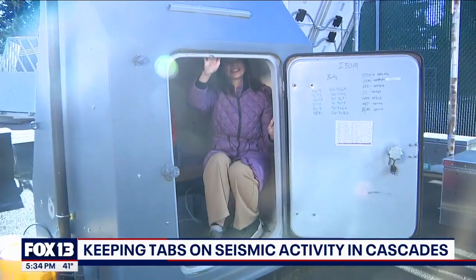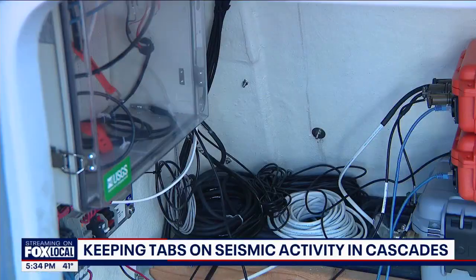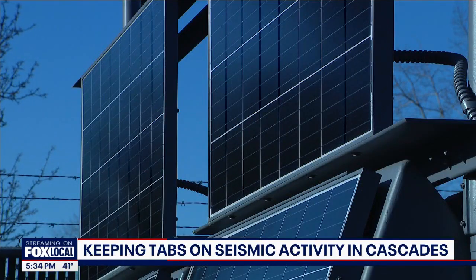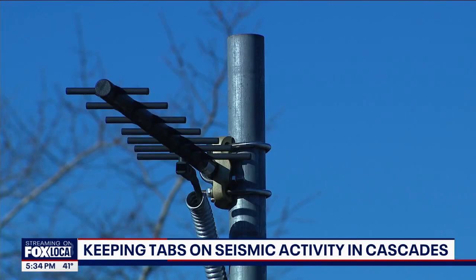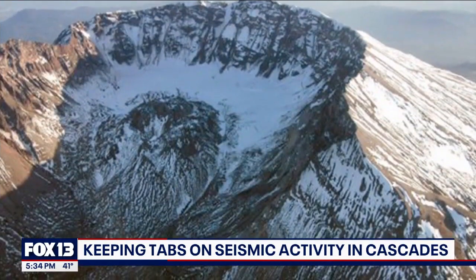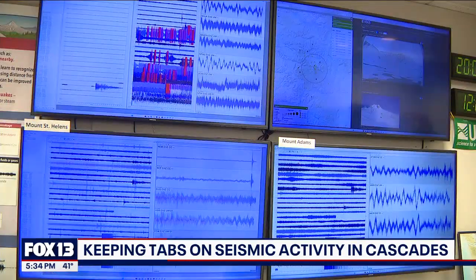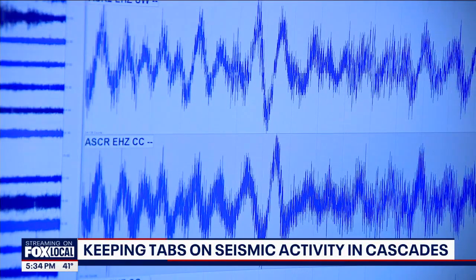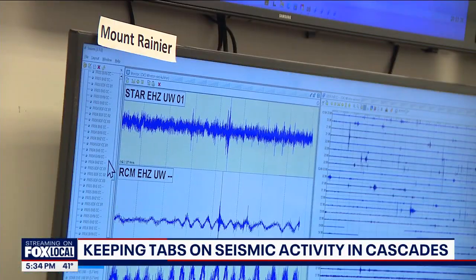We're not just learning how scientists track our region's active volcanoes — we are taking a quite literal inside look at a monitoring station. All that technology I just showed you, well, this is its hub, packed full of batteries equipped with 200-watt solar panels, a camera, and an antenna stretching 12 feet high. This is needed to transmit evidence of any tremors or unusual activity. To be able to read it, we have to convert it into a digital signal, and then that digital signal goes into the box, and there's a radio transmitter that then transmits that data back to us here at the observatory.